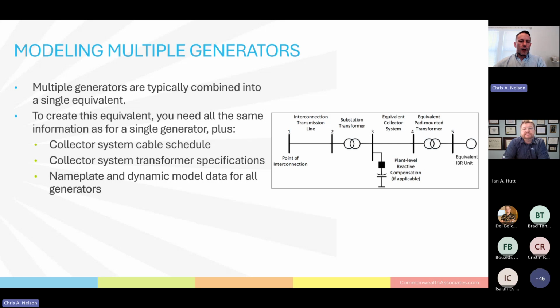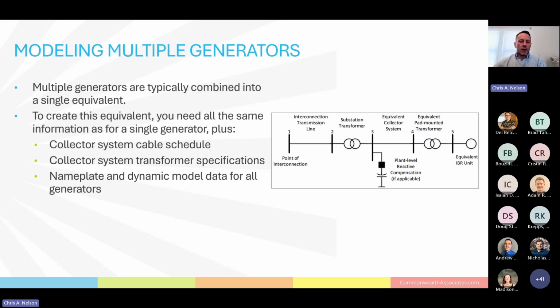So we talked about a single generator—somewhat complicated, but it gets a lot more complex with multiple generators, because most utilities, I think every utility, don't want you to model all your generators. There's too many bus numbers; it makes everything run slower and worse. So they usually want a single generator, single cable, single transformer representing your whole site in their model. If you have, say, a solar and a battery, you might have two different generators, one for each, but they want you to combine into as small an equivalent as you can.